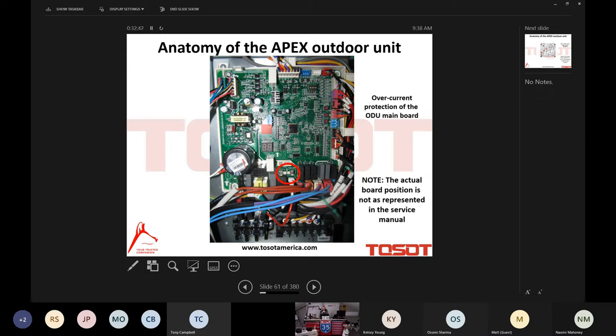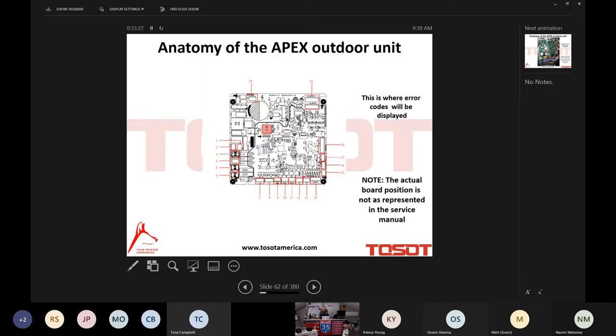Once again, overcurrent protected with a fuse. Now listen up. I'm not going to give you the same rant that I already gave you about surge protection, but I will make this note. With a split system like the Apex is, you're bringing a 208, 230 volt circuit to the indoor unit, right? And you're also bringing a separate and unique 208, 230 volt circuit to the outdoor unit, as you see here. So that really requires two surge protectors, one on the outdoor unit and one on the indoor unit. So something that you want to stress to your customers as well. Is it necessary? No. I just highly, very strongly as I possibly can recommend it.